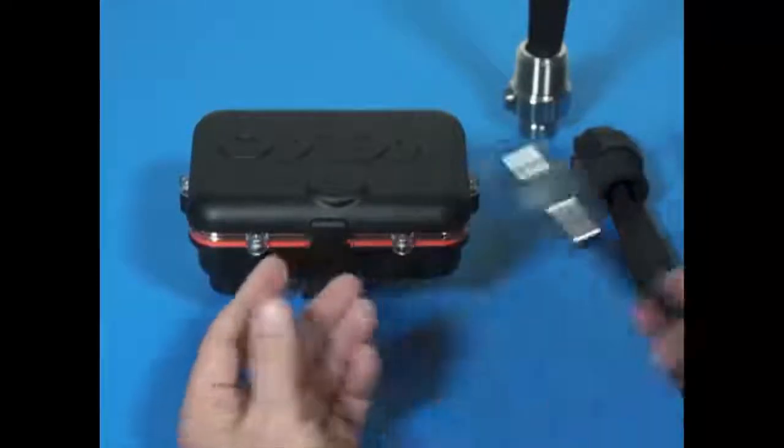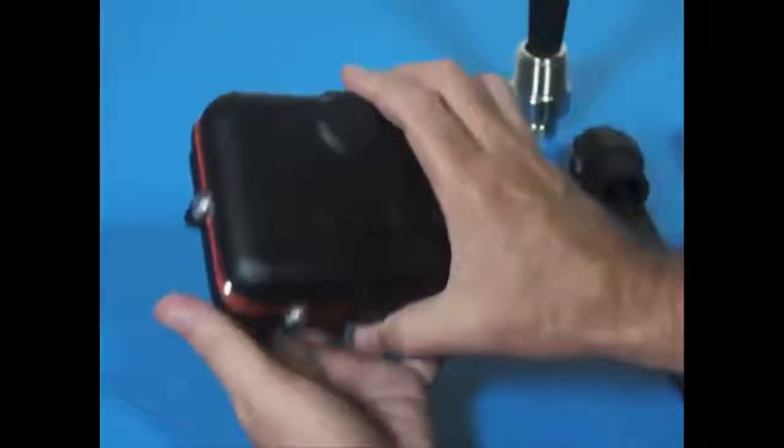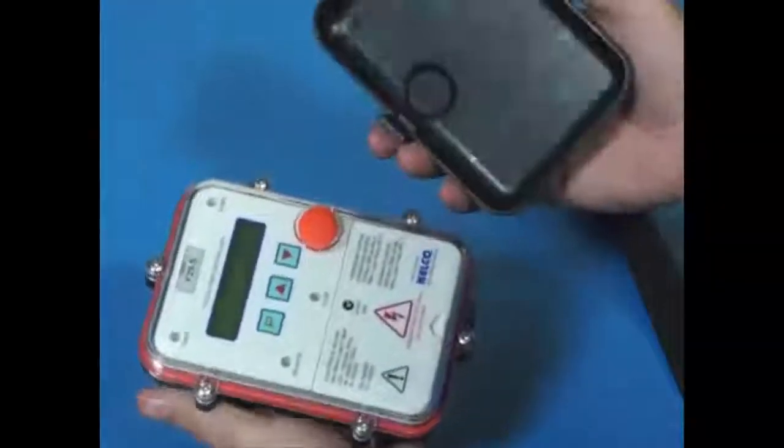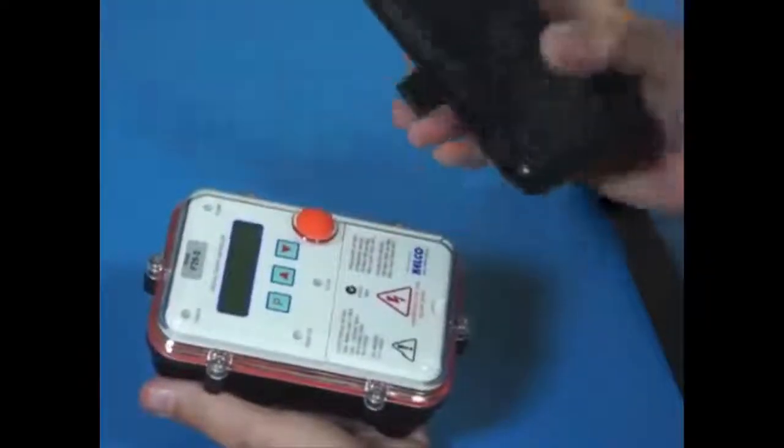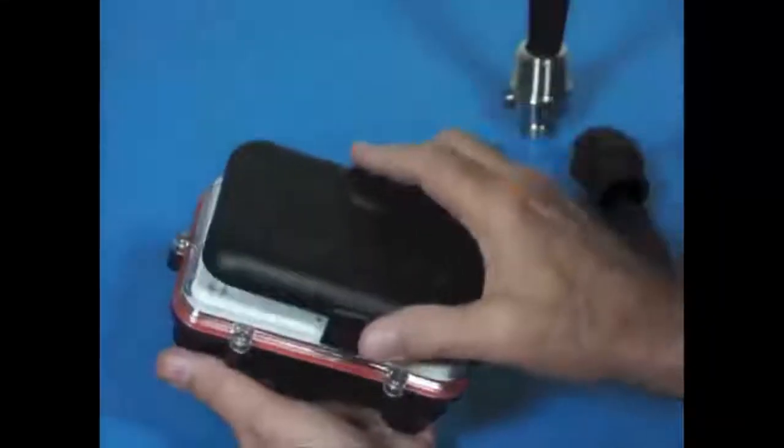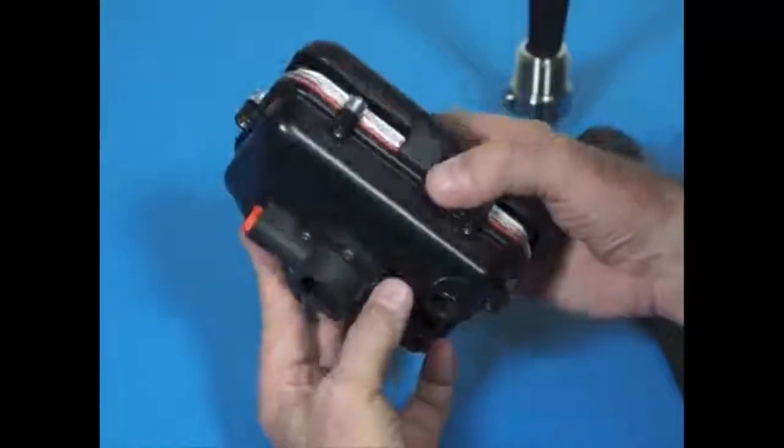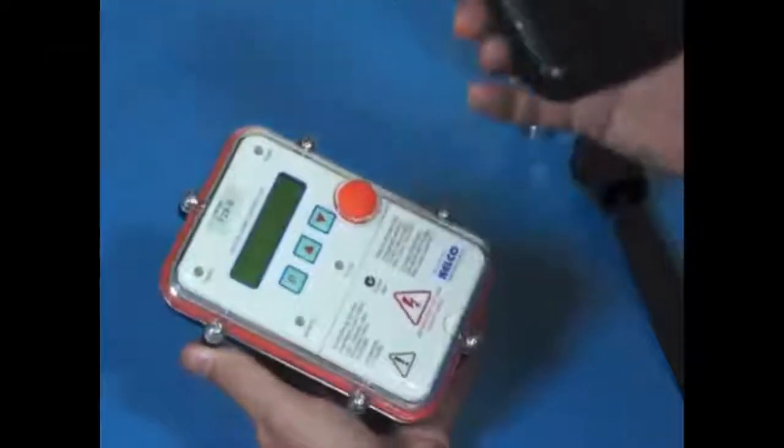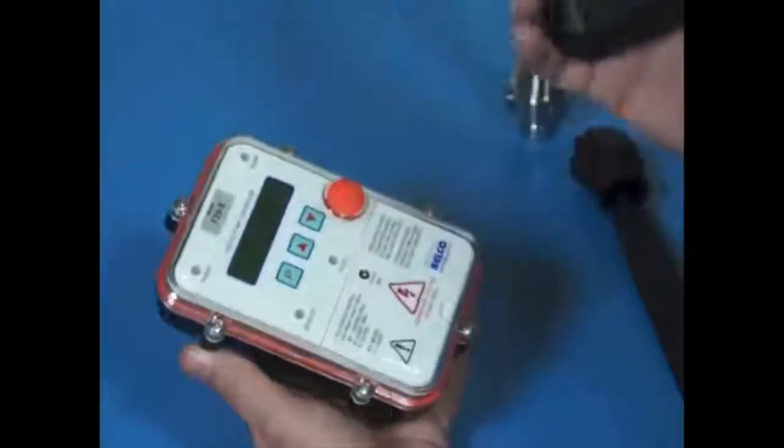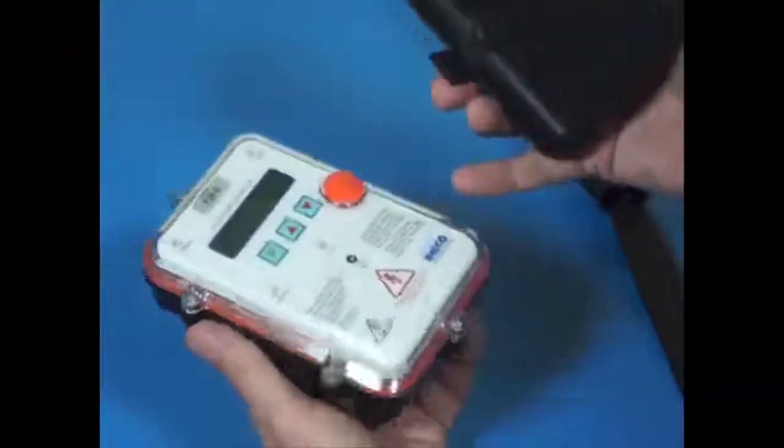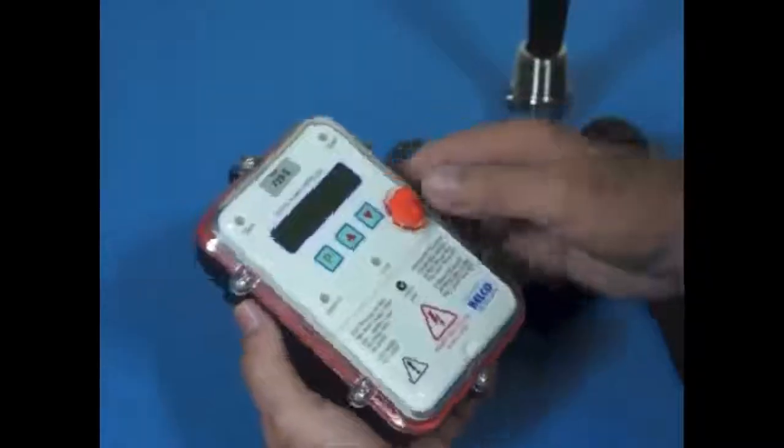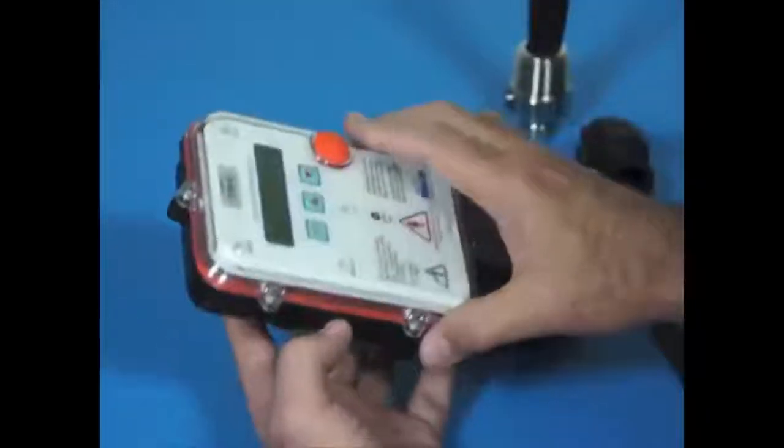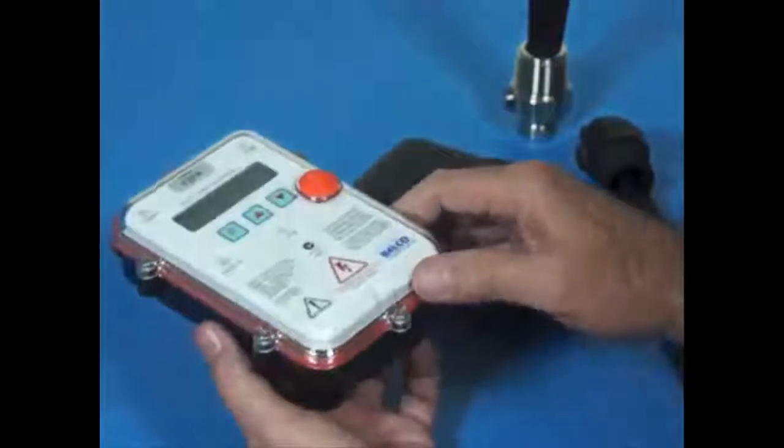The electrical module on the F29 has a protective clip-on skull cap cover that protects the clear electrical housing cover from the elements. This enables the flow switch to be used in fully exposed outdoor applications without the slightest concern about degradation of the LCD screen or the clear lid or ingression of moisture into the enclosure. The enclosure is IP67 rated and the lid is secured on by six captive stainless steel screws bedding down on a rather oversized gasket.